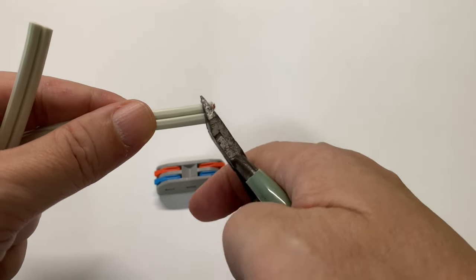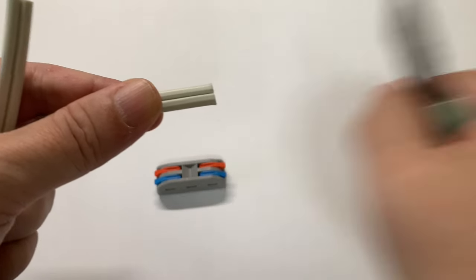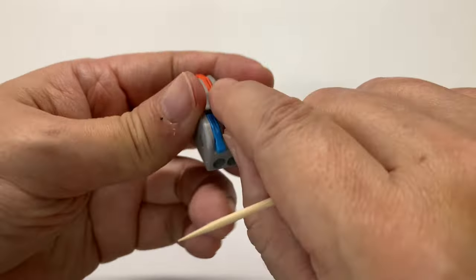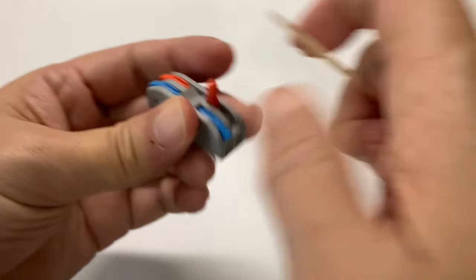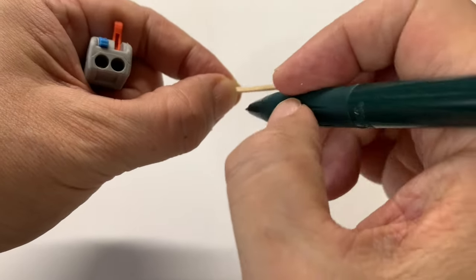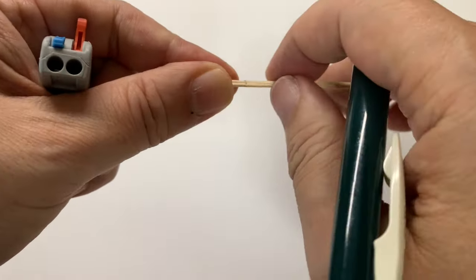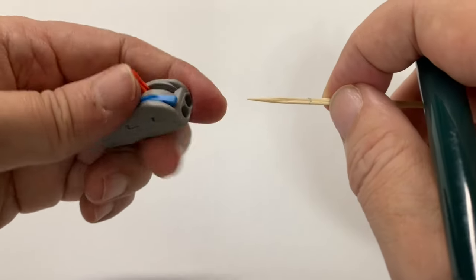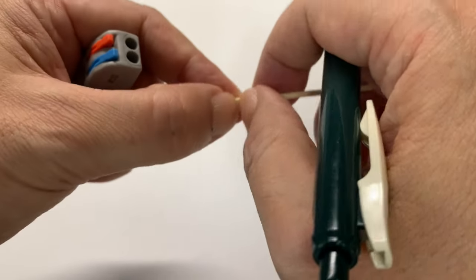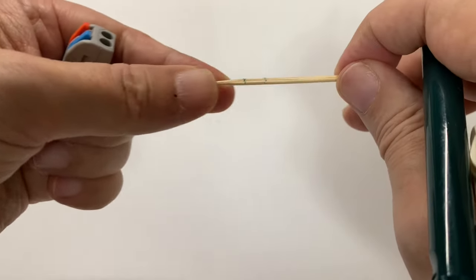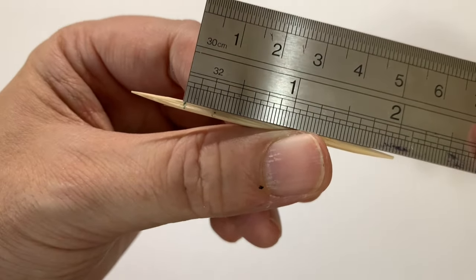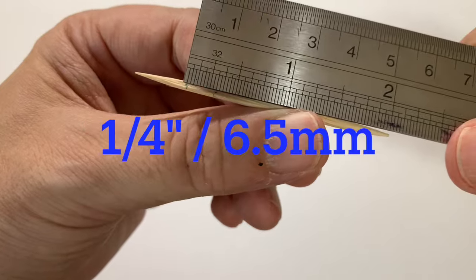Let's prepare the wires to be spliced. First, make sure the tip of the pair of wires are cut flush to each other. Then let's determine the depth, both when the lever is open and closed. The measured depth of the clip is around one quarter of an inch, or six and a half millimeters.